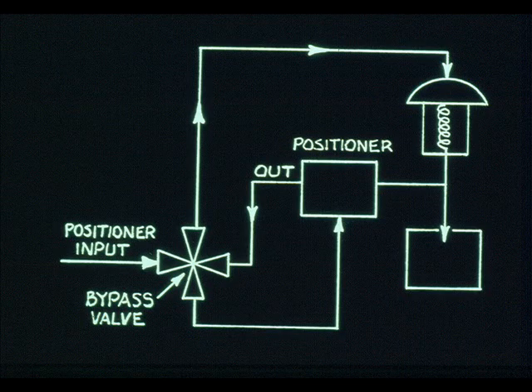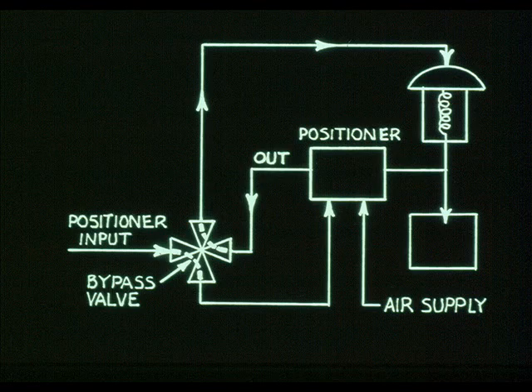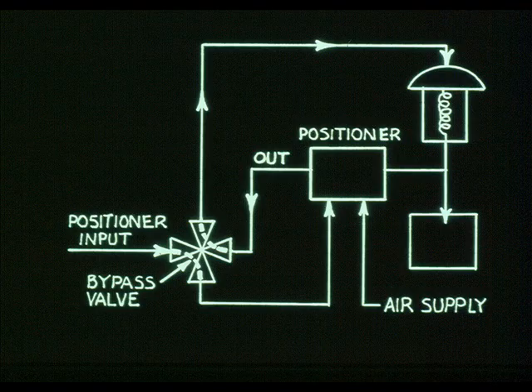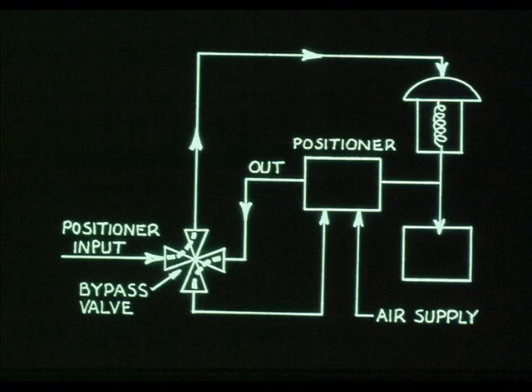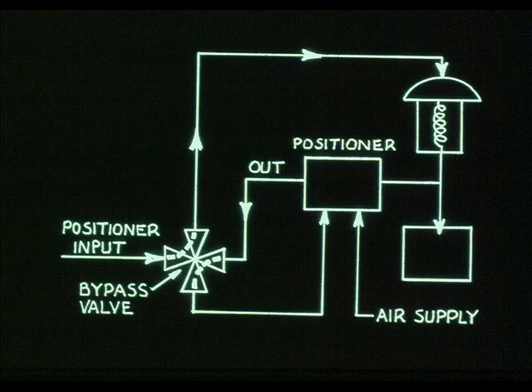Some valve positioners have a bypass valve. When the positioner is in service, the input is routed to the positioner bellows and the positioner output is routed to the actuator. When the positioner is bypassed, the input goes directly to the actuator, and the positioner relay, flapper nozzle, and other parts can be removed and repaired.